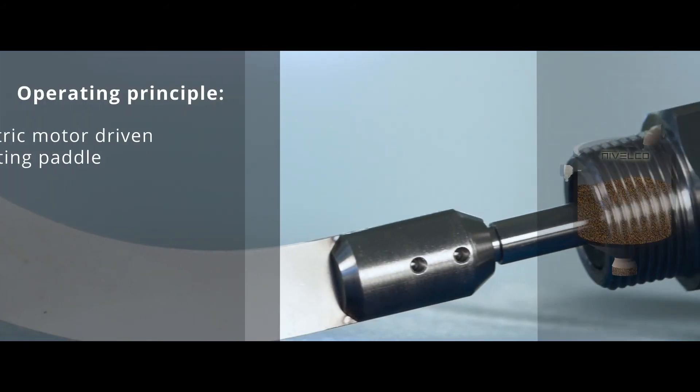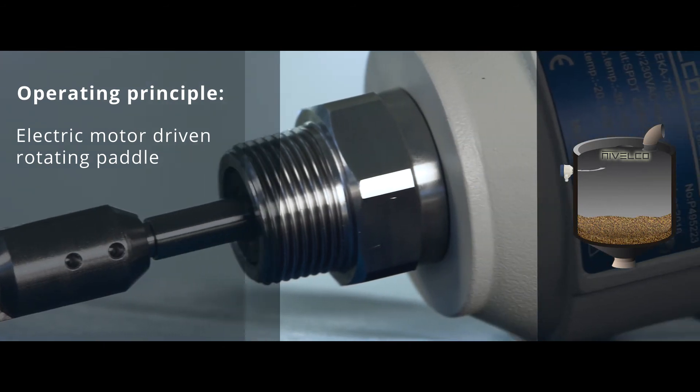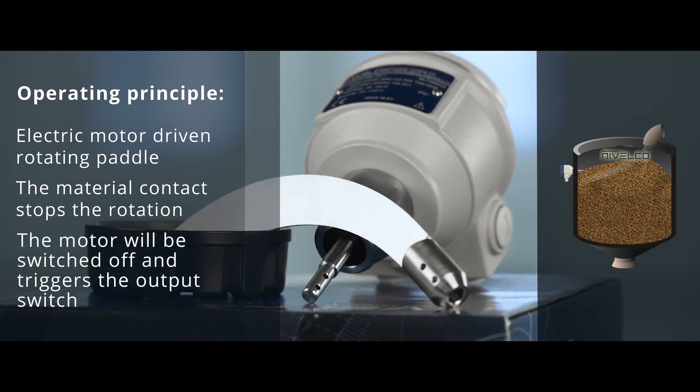A small power electric motor drives the paddle which rotates freely in the absence of the material. When the paddle is immersed by the material reaching it, the motor will be switched off, at the same time triggering the output contact switch.